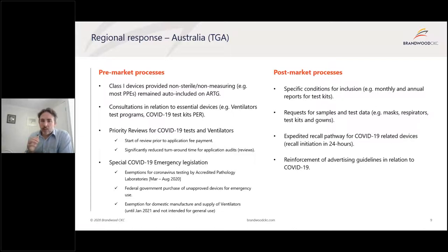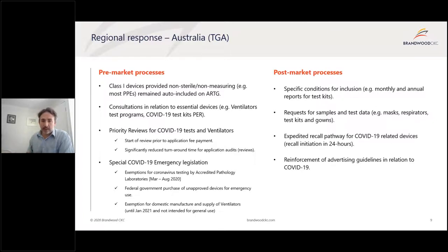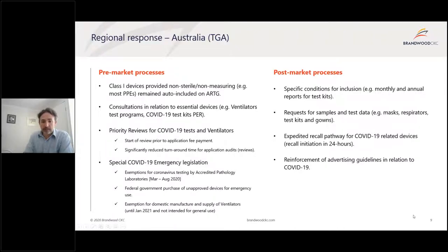On the post-market side, the big development was that TGA made many conditions for approval on expedited devices. They did an initial assessment affirming safety and effectiveness from available data, but required manufacturers to address post-market conditions for long-term use. TGA also took samples of COVID-19 diagnostic tests and some PPE articles to test them and prevent substandard product from entering the market. They implemented an expedited recall pathway — COVID-19 products found unsafe required recall within 24 hours — and issued special advertising guidelines for COVID-19-related products.